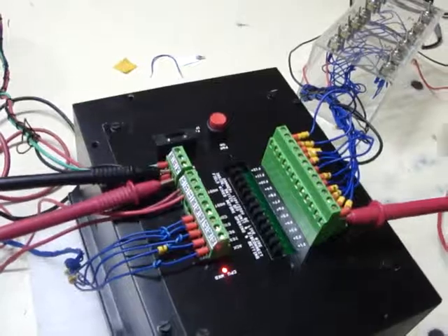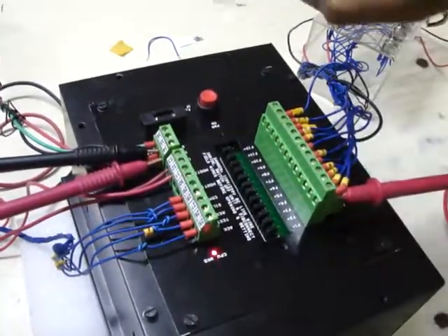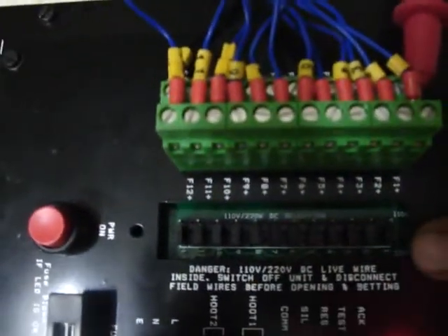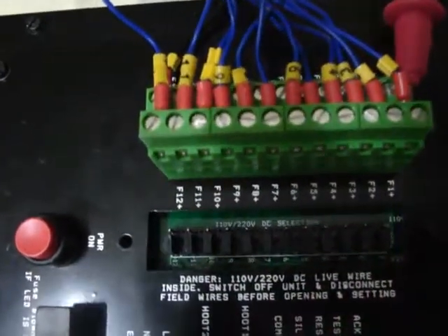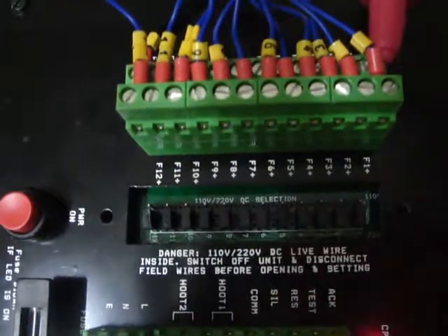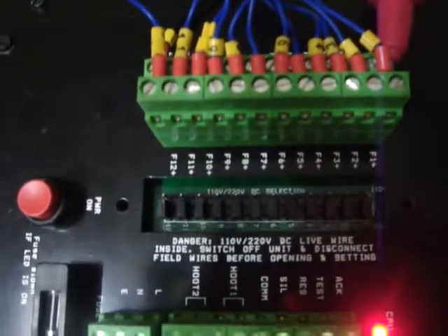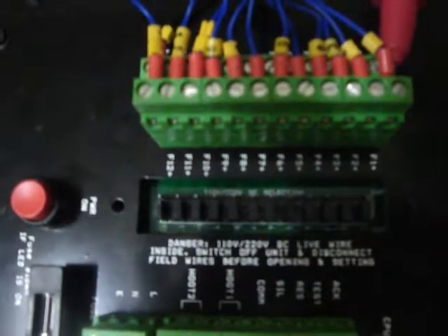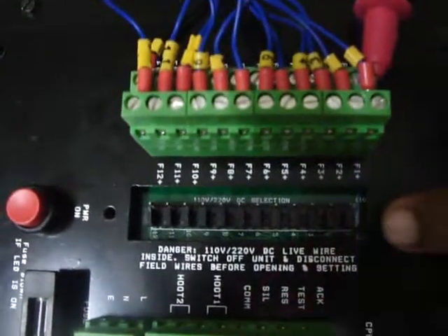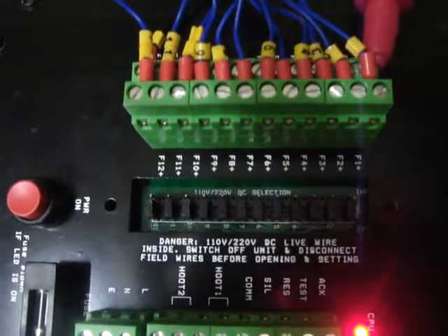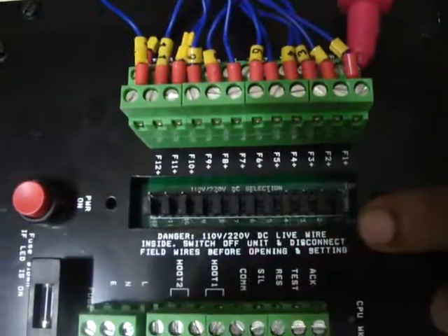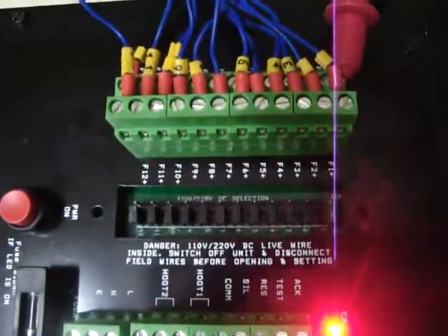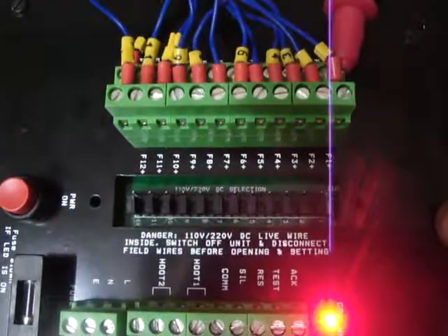Now let me give 220 volt DC. For this annunciator, the fault input is selected as 220 volt DC for each individual window through this jumper. Please be careful. The selection of the jumper should not be done live. The power should be switched off, and all the fault inputs should be removed before selecting the jumper. Also, we have pre-configured 104 annunciators with 220 volt DC input and the balance annunciators with 110 volt DC input, as per your purchase order.